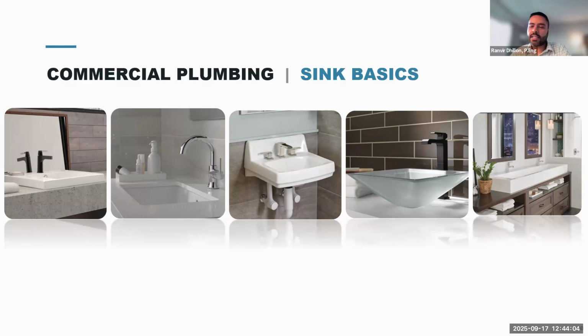It's just not designed to drain well. Yeah, so in that case, that would be something that would be driven by the maintenance schedule, by the management of the facilities. That's something that can also be driven by using something that still meets the LEED criteria. So 0.35 is LEED 4.0 and 4.1, but in certain cases, you do get points for using 0.5, and an aerated outlet might help sort of move more water in that case. Perfect. Thank you.